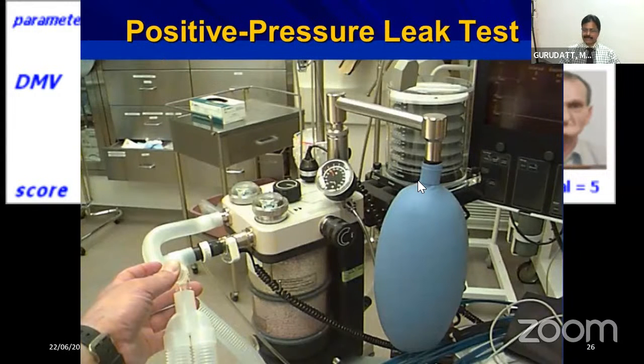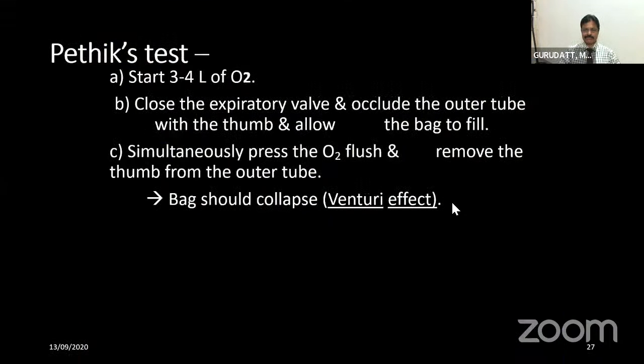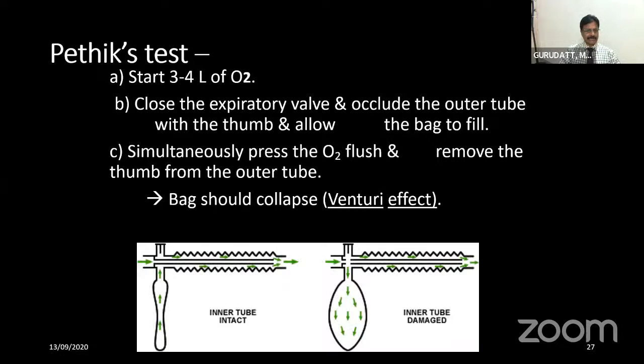The other time when you use this oxygen flush is to check for the integrity of the inner tube of the Bain circuit. So we all know the Pethik's test. When we are using this Pethik's test, we also use the oxygen flush. I was telling you that accidentally, if you activate the oxygen flush, 35 to 70 liters of oxygen with high pressure can go to the patient and can produce barotrauma. But this has also been thought about in the case of Draeger machines.